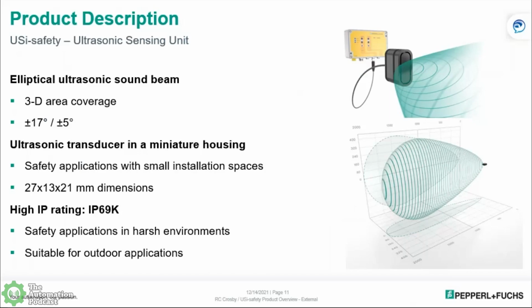Again, small housing, small installation footprint, high IP rating of IP69K. So it's perfect for outdoor, perfect for wet environments as far as the transducer is concerned. And because of the uniqueness of the elliptical sound cone, you can get that thing turned to where it's just off the floor or just off a flat surface, but yet still parallel to it. So you can get really tight, good coverage up against hard stops, if you will.